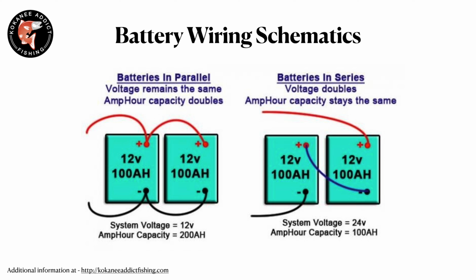One option, if you want to increase capacity and say you have just a 12 volt system, is to wire your batteries in parallel. Wiring two batteries in parallel, as in the image on the left, increases total capacity, the total amp hours, from 100 to 200, while staying at 12 volts. For my system, it's 36 volts, so I need 3 batteries wired in series, each one adding onto the system. So I've got three 12 volt, 100 amp hour batteries, giving me a 36 volt system at 100 amp hours.